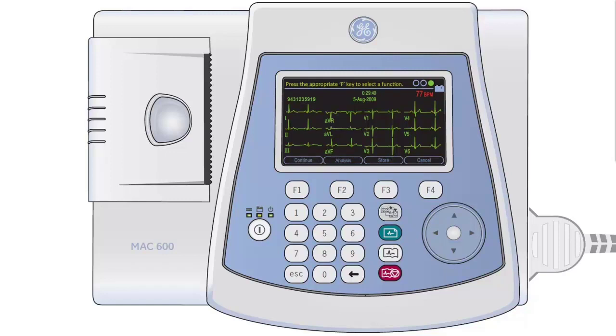The automatic interpretation can be viewed by pressing the F2 button. If the captured ECG is unsatisfactory, press the F4 button to cancel, which will take you back to the previous monitoring screen, allowing you to capture the ECG again.